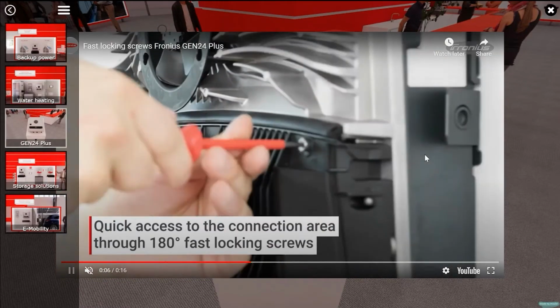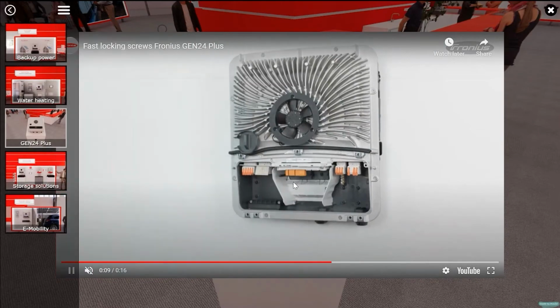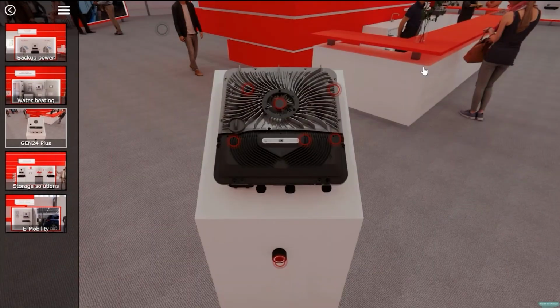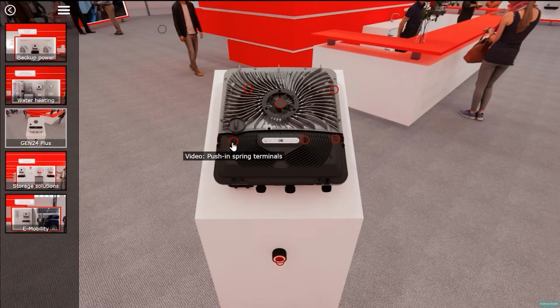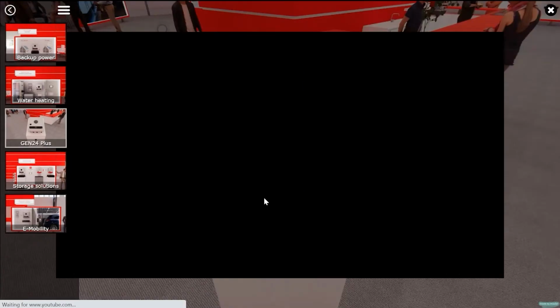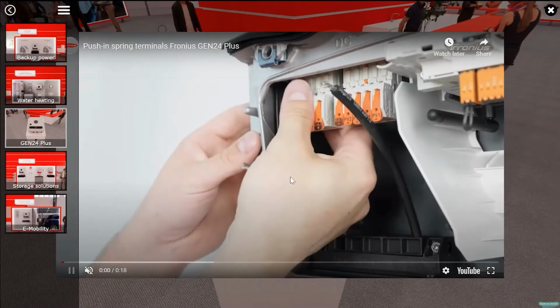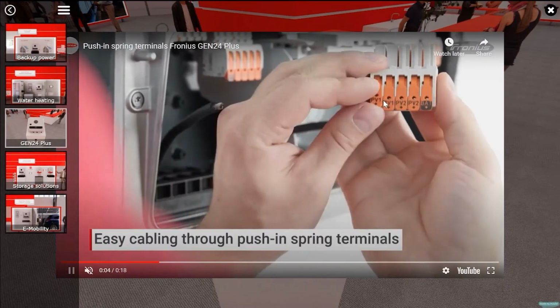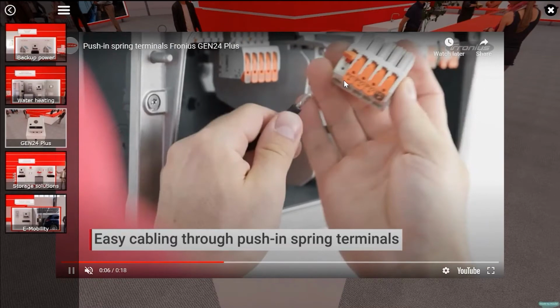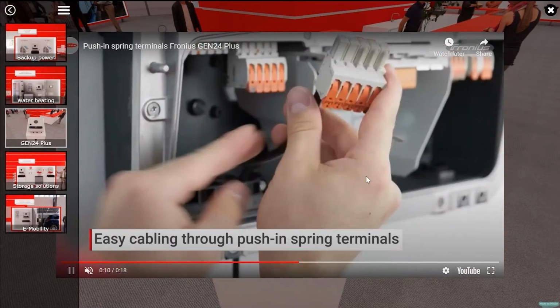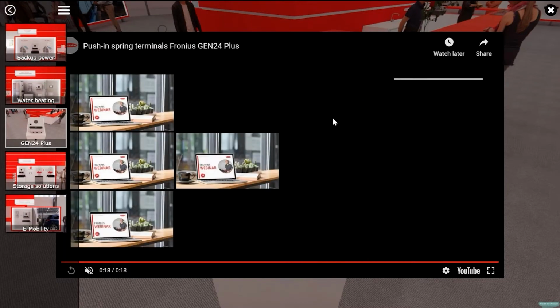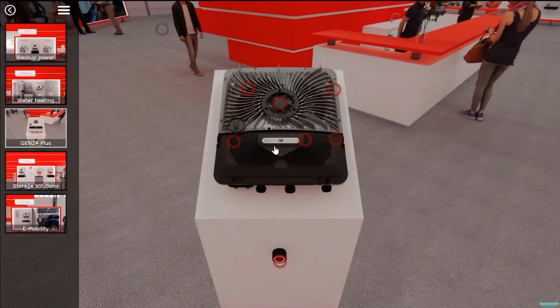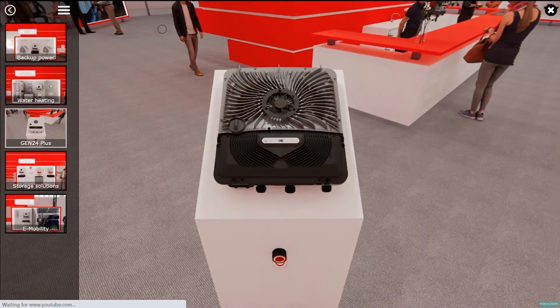We wanted to make sure this is nice and quick, and then you see all the DC and AC side. We have a new connection area using push-in spring connection. If you look at this section, you can remove this bottom part, and then there's a spring release clamp where you just put the DC cable in. It's also applicable for the AC, and then you put the terminal back. We wanted to make sure the space is still large, so the installer can easily go in and change or remove the cabling. We wanted to keep a lot of space.